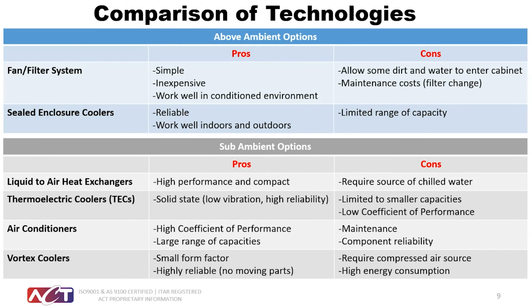Looking at sub-ambient technologies, liquid-to-air heat exchangers offer high performance in a compact package. Liquid-to-air heat exchangers rely on a dedicated source of pumped coolant in order to function, which can be a limiting factor in their use. Thermoelectric coolers, or TEC for short, take advantage of the Peltier effect and offer low vibration, solid-state cooling in a compact form factor. A drawback is that the coefficient of performance of thermoelectric coolers is lower than competing technologies, which makes it better suited for low-power applications.